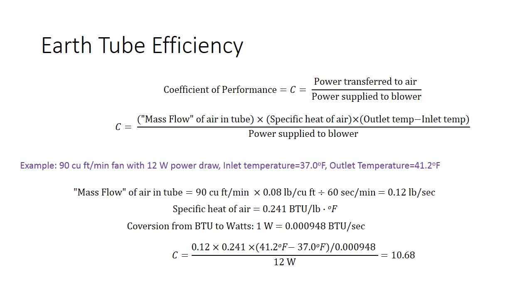As a concrete example, I've got a 90 cubic foot per minute fan. It draws 12 watts. Let's say the inlet temperature was 37 and the outlet temperature was 42. The mass flow of the air in the tube is 90 cubic feet per minute. The density of air is 0.08 pounds per cubic foot. Divide by 60 to convert from minutes to seconds. We get a mass flow of 0.12 pounds per second, which is a surprising amount considering you don't think air weighs very much, but it actually does.